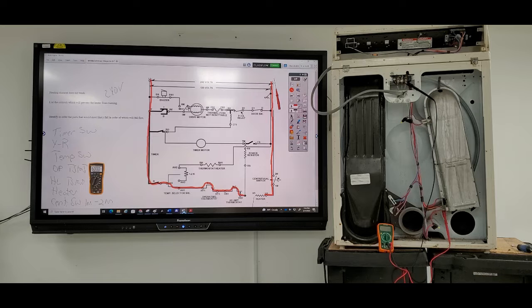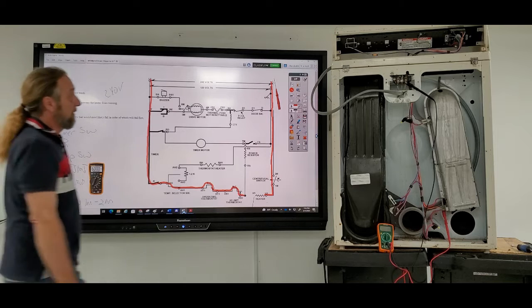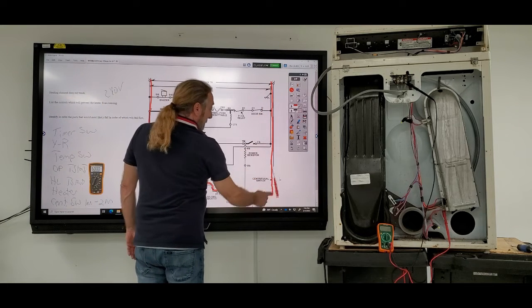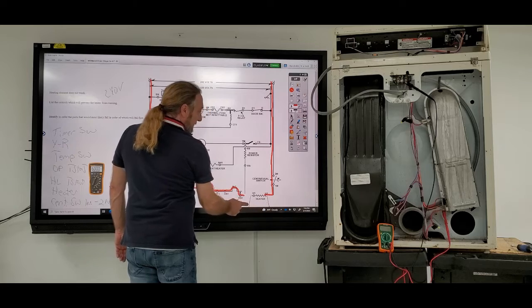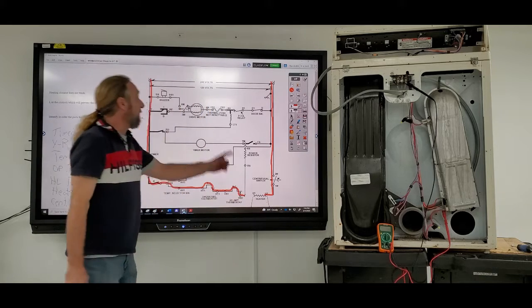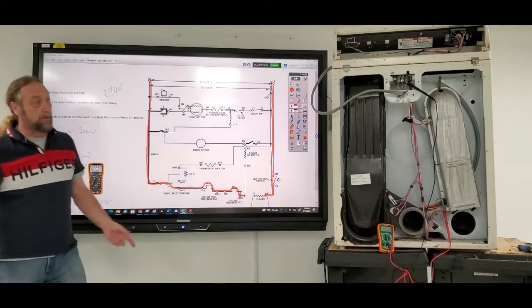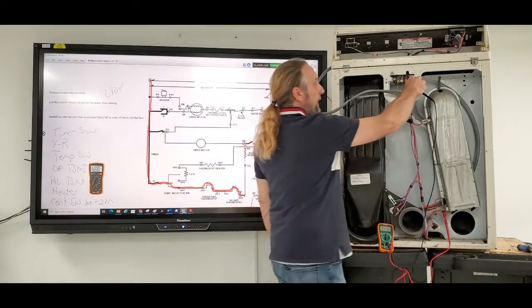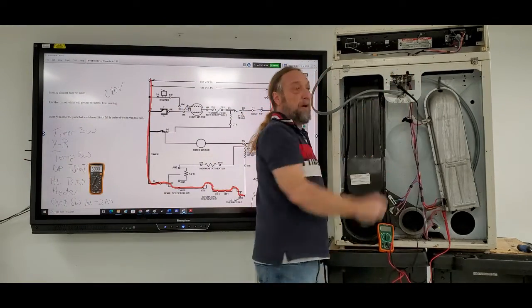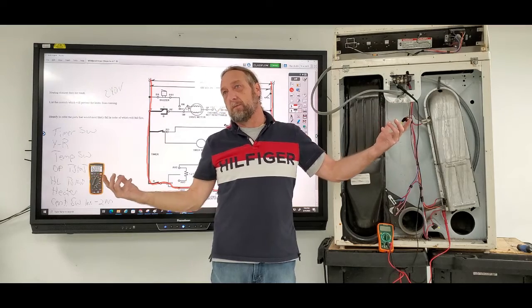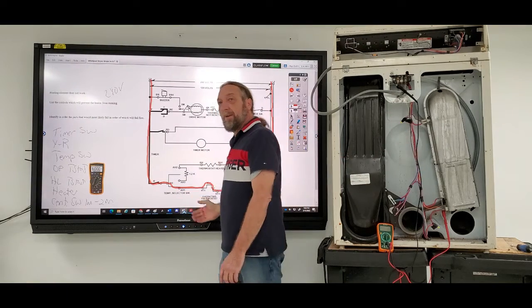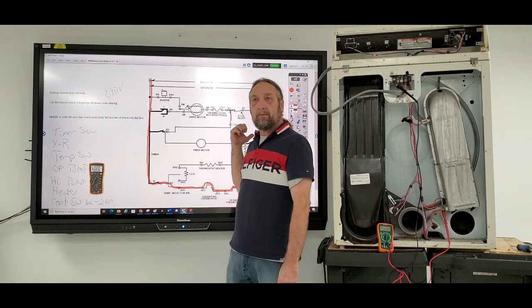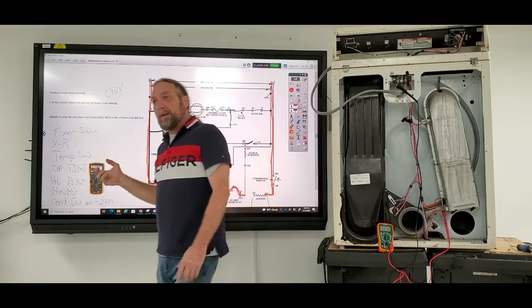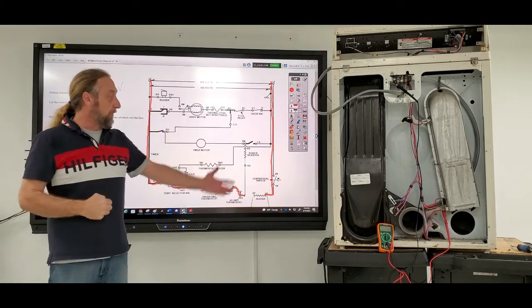Now, if I did not get voltage, I move this one back to here, and take my black lead. Yes, I could go back here. I could take this one and move it over here and say, oh, now I got 240. Okay, well I know my problem is on this side because it wasn't on that side. So now I got 240, that tells me the centrifugal switch is good.